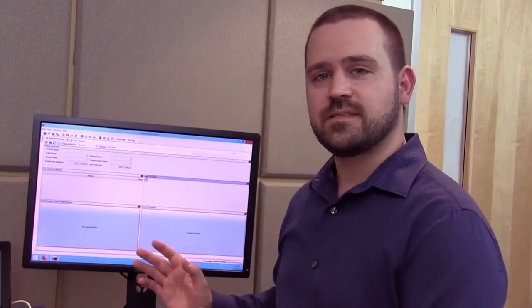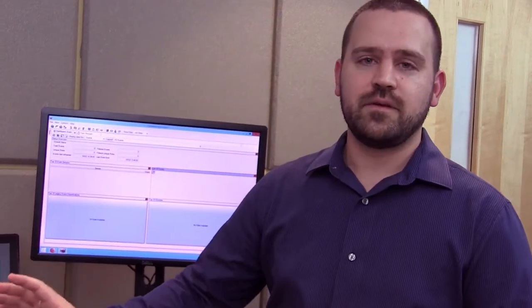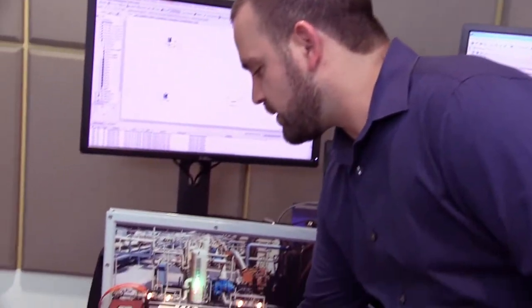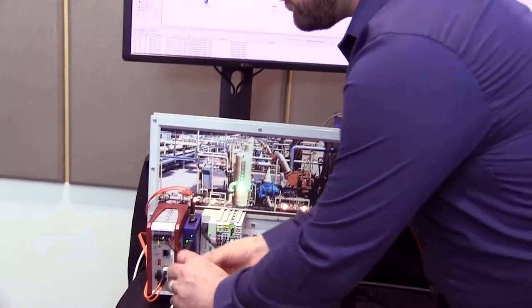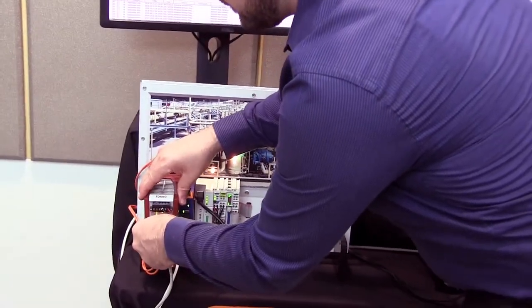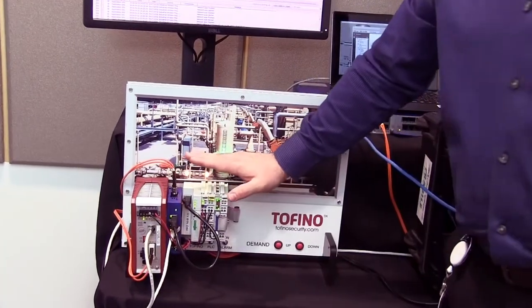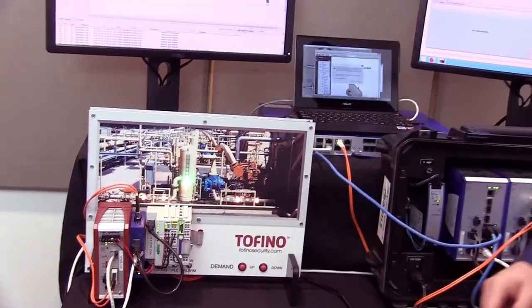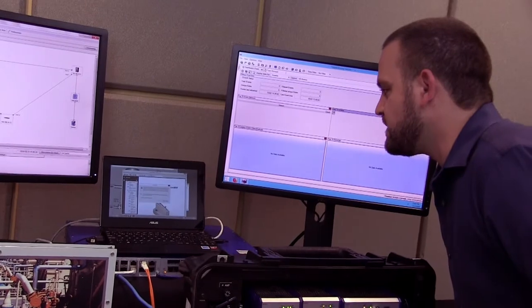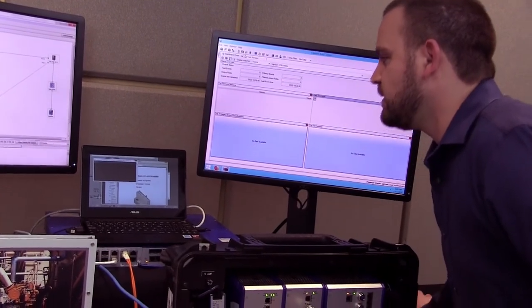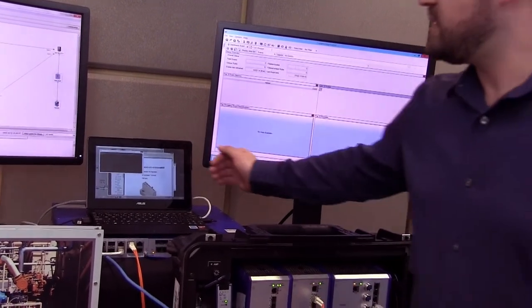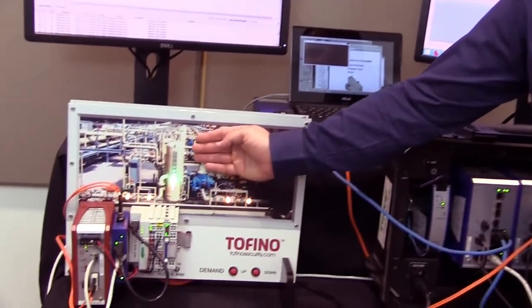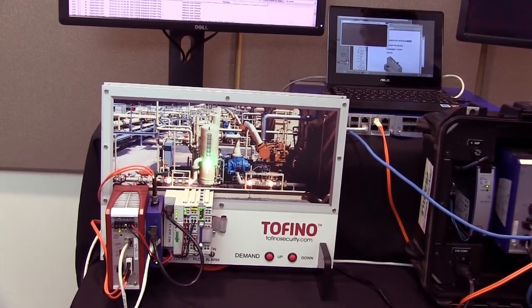Now let's see what happens when we run that same attack against that PLC through the Tofino firewall. So if we unplug and go through this Tofino firewall, we're now protecting this PLC. As I run this attack, you can see the attack is executing, but nothing is actually affecting the programmable logic controller.